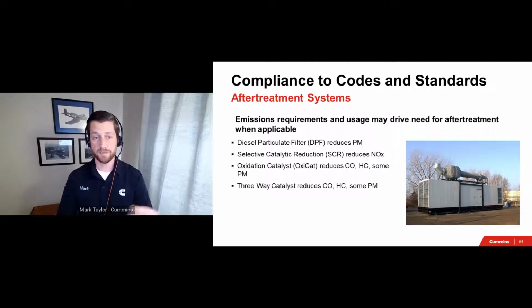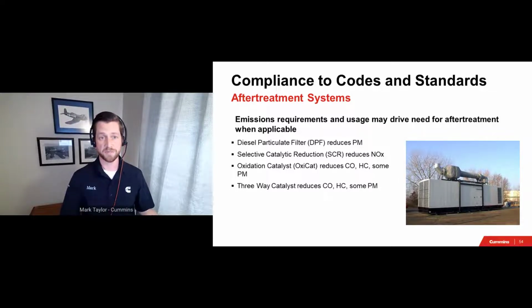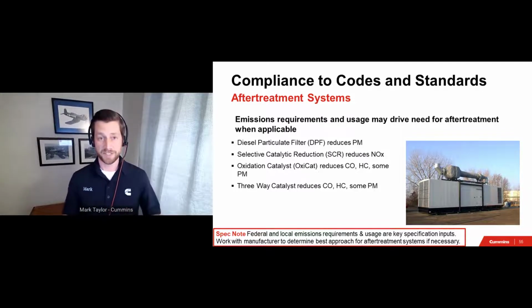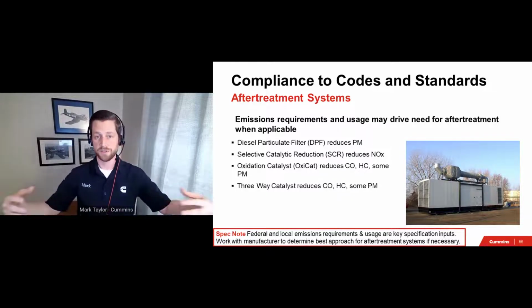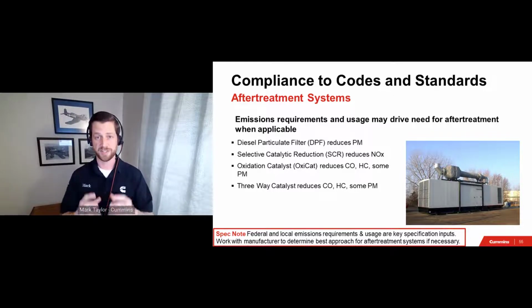So far, I've covered the major emissions constituents that are present in different exhaust streams from diesel or gaseous fuel generators, and the federal and local requirements around them. At times, it may be necessary for a generator set to include one or more after-treatment technologies to meet these requirements. Particulate filters may do as their name describes, reduce particulates, and there's a whole slew of different technologies and bolt-on attachments, basically, for lack of a better term, that would reduce different constituents. But that all said, avoid specifying specific emissions technology, as that may over-constrain an otherwise well-constructed generator set specification.